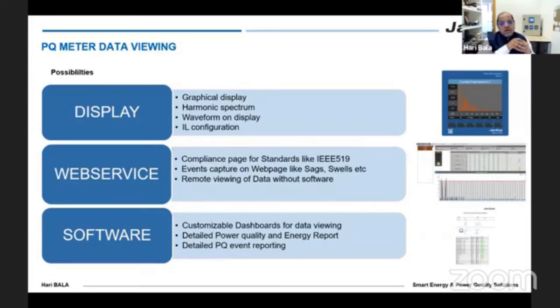And then there is also a possibility through web service on the meter. So by typing the IP address of the meter, you can access what you want to do in the meter, because it's very difficult to show many compliances of standard on the meter. So what we have done is we have created applications inside the meter, like our mobile apps. We have created an application inside the meter where it can give you compliance to those particular standards, because quite a lot of calculations and statistical evaluation needs to be handled by the meter. So we do that through an application, and then it can be viewed through the web service. I'll try to show you how it will also look like.